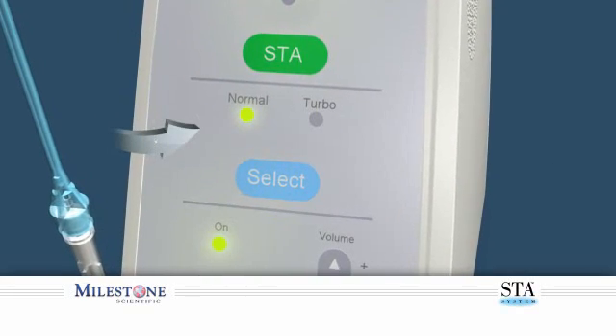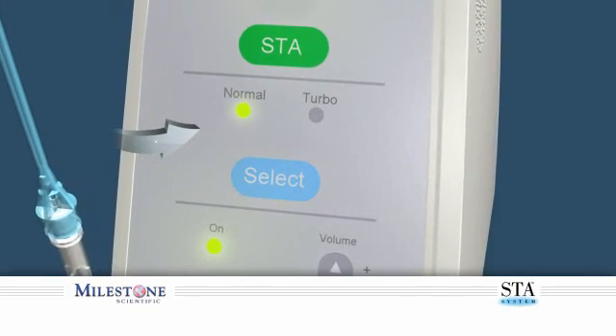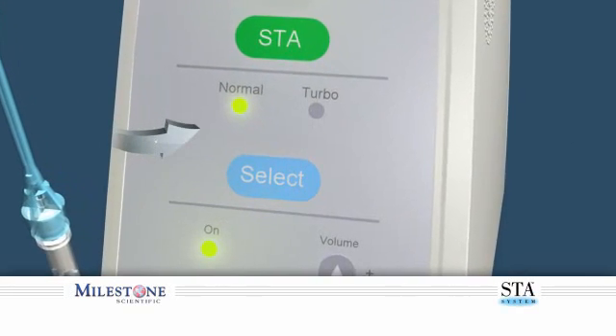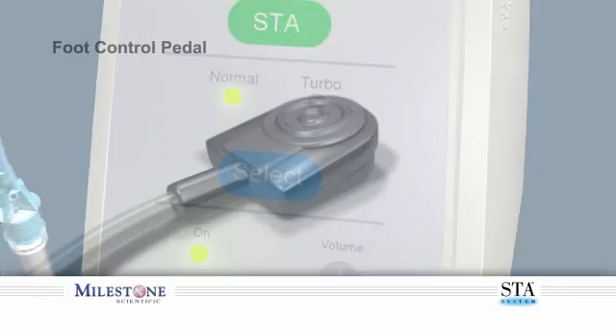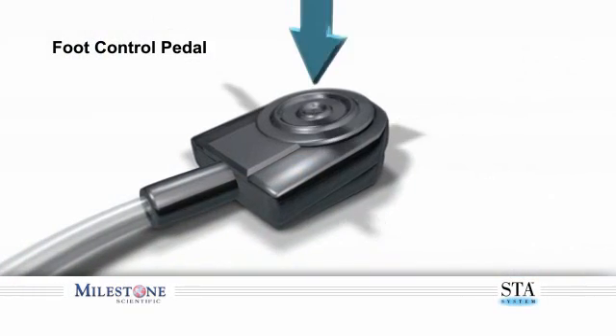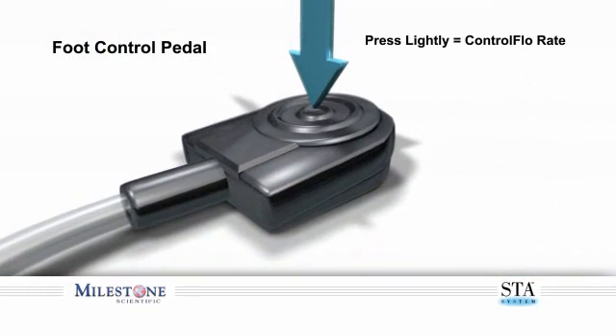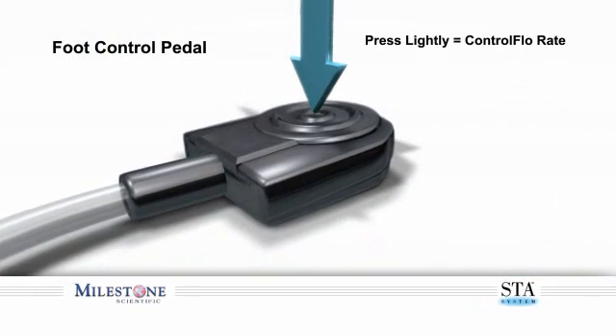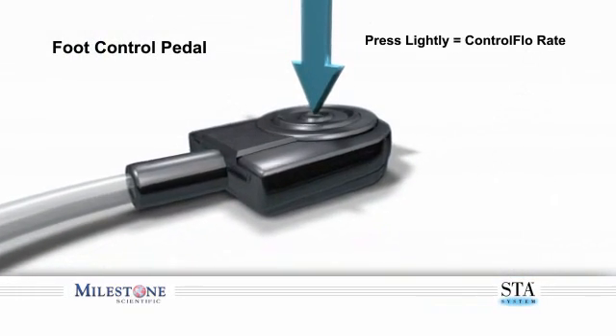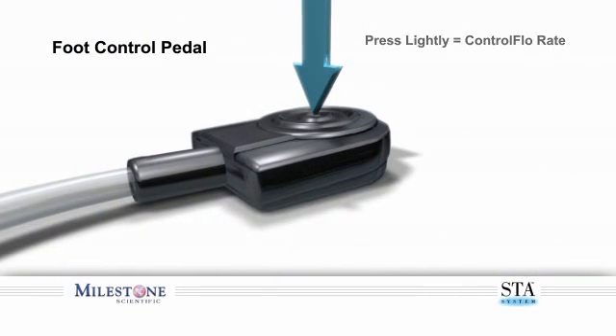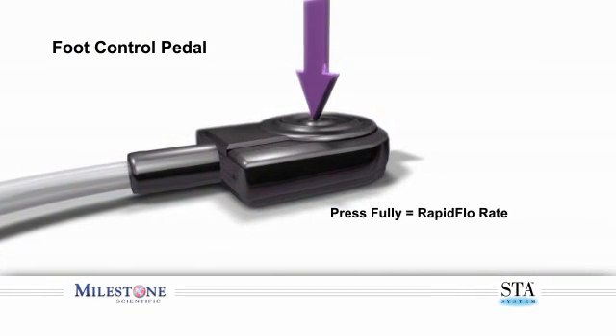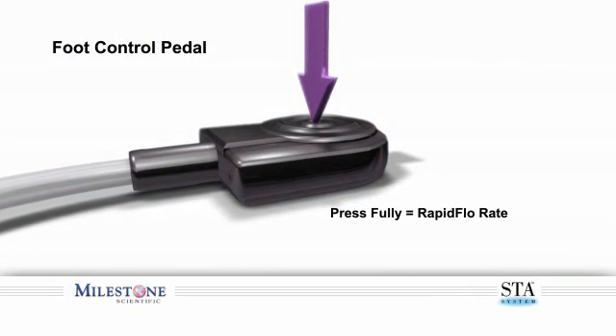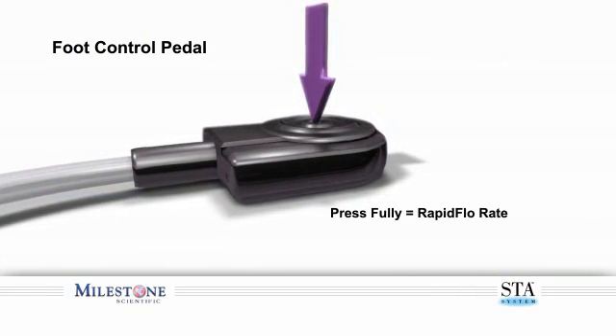In the normal mode, the foot control has two distinct positions. Depressing the foot control lightly allows you to enter the ControlFlo rate. Fully depressing the foot control allows you to enter the RapidFlo rate.